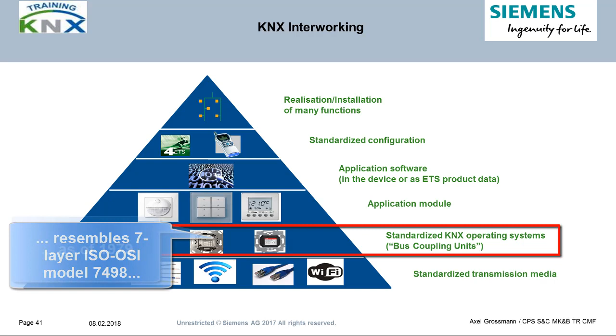Layer 2. To exchange data within a medium, the so-called bus coupling units, short BCUs, are required. The operating systems of these BCUs must be KNX certified to ensure compatibility with the protocol stack. The BCU stacks are designed in conformity with the International Standard for Serial Communication ISO 7498 as of 1979, very often called the 7-layer model of serial data exchange. It has been unchanged since then, which underlines its universal importance for all kinds of digital communication of the present.